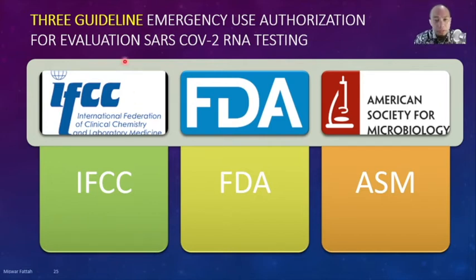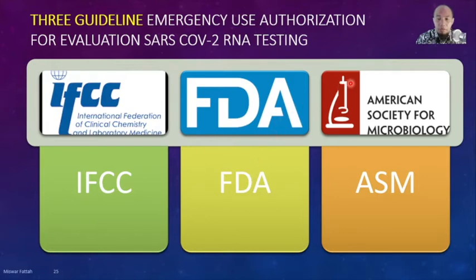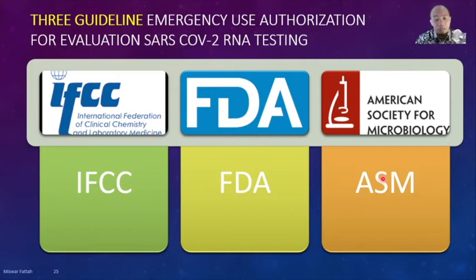Three guidelines are now available for emergency use authorization evaluation of SARS-CoV-2: the newest guideline from IFCC (International Federation of Clinical Chemistry and Laboratory Medicine), from FDA, and from the American Society for Microbiology. This guidance is not meant for validation of laboratory-developed tests or for validation of new tests by manufacturers, but focuses on verification. Laboratories should verify the analytical performance claim of regulatory-approved molecular testing, including specific parameters, before routine use.